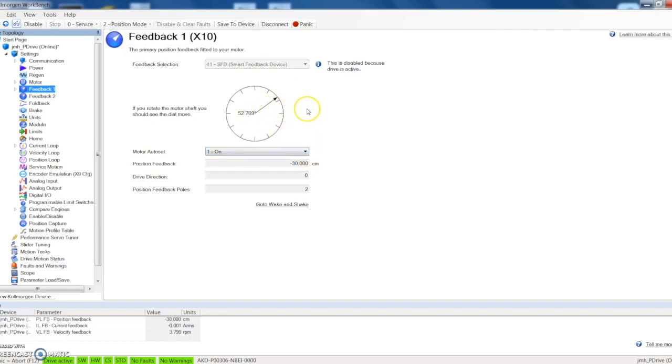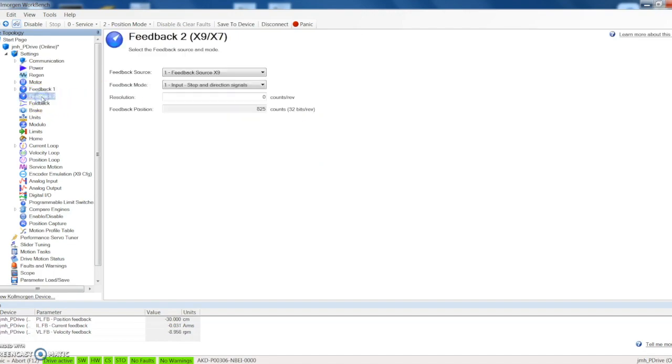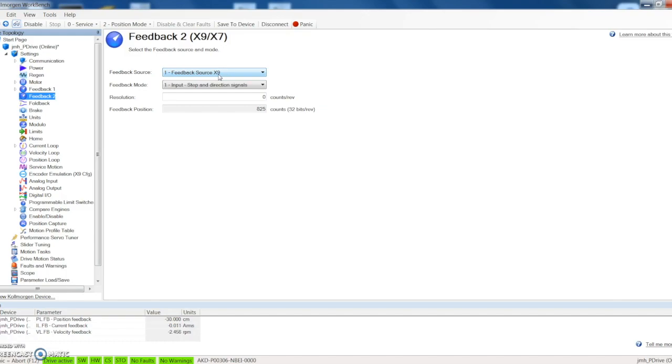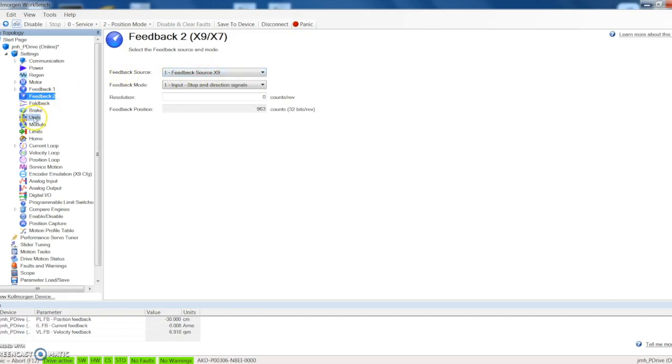Feedback one: you can see we're using the smart feedback device motor set is on. This has given us our current degree of the shaft position. Feedback two: that's looking at our X9 port that's on the drive. In our X9 port is connected to a simulated encoder knob so we'll be able to use that. You can see if I turn the knob that my counts change down in feedback position.